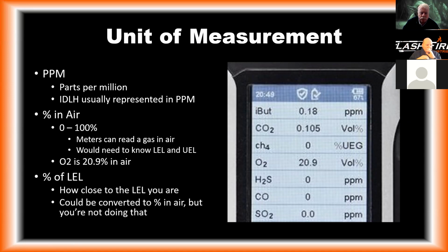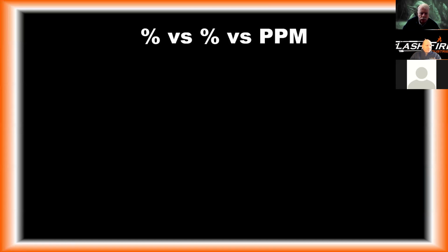And I have a couple of slides that will explain this a little bit better. But your meter, that LEL sensor, the explosive level combustible gas sensor, is reading percent of LEL. So 0% LEL to 100% LEL. It is not reading 0% in air to 100% in air. The number could potentially be converted to air, but we're not doing that. We just care about, are we at that lower explosive level or not?